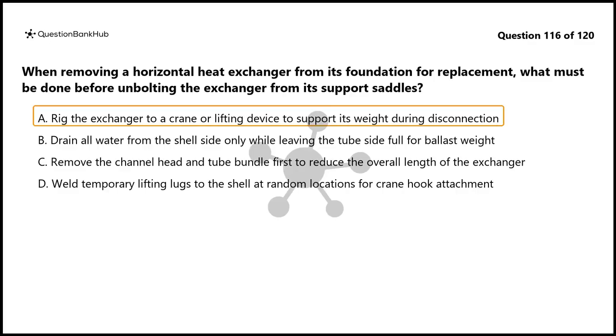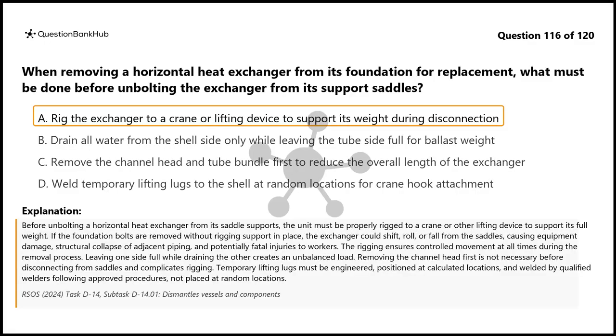The correct answer is A. Before unbolting a horizontal heat exchanger from its saddle supports, the unit must be properly rigged to a crane or other lifting device to support its full weight. If the foundation bolts are removed without rigging support in place, the exchanger could shift, roll, or fall from the saddles, causing equipment damage, structural collapse of adjacent piping, and potentially fatal injuries to workers. The rigging ensures controlled movement at all times during the removal process.